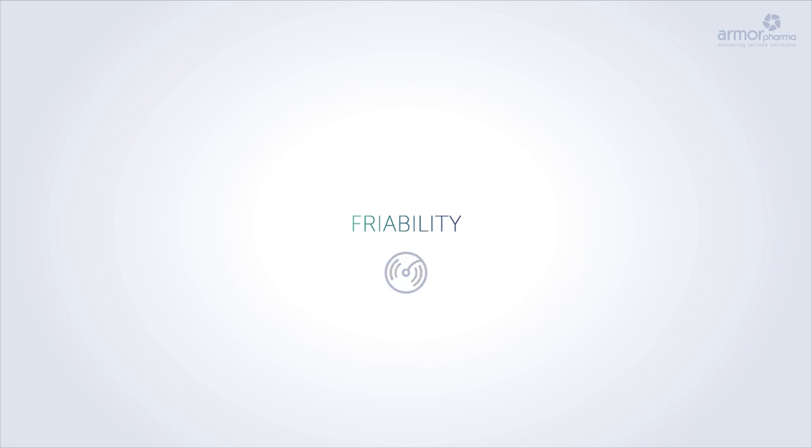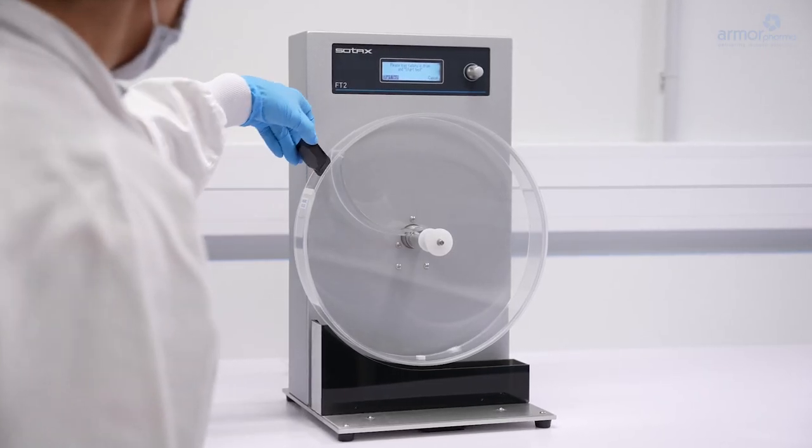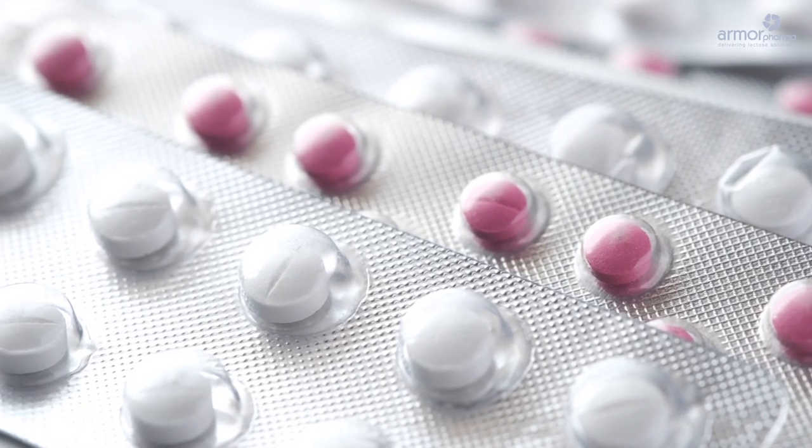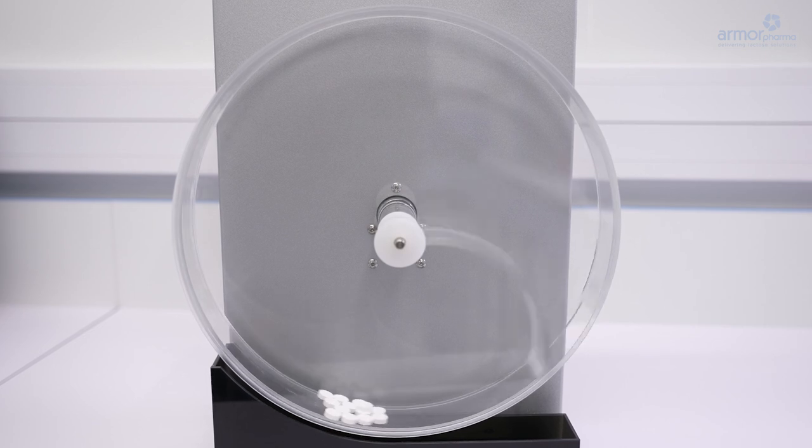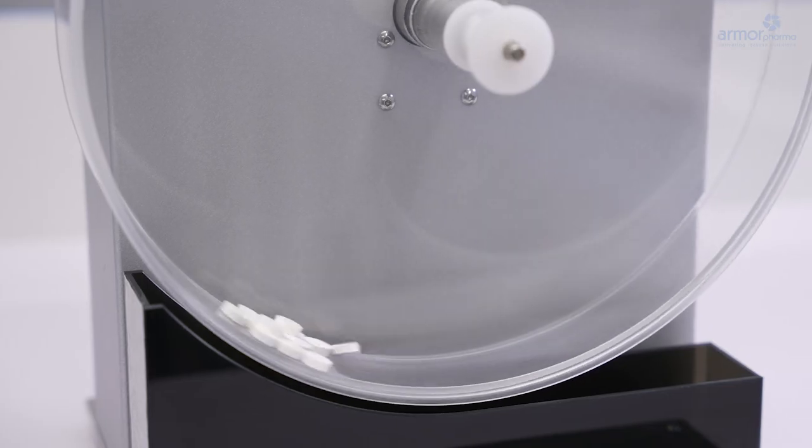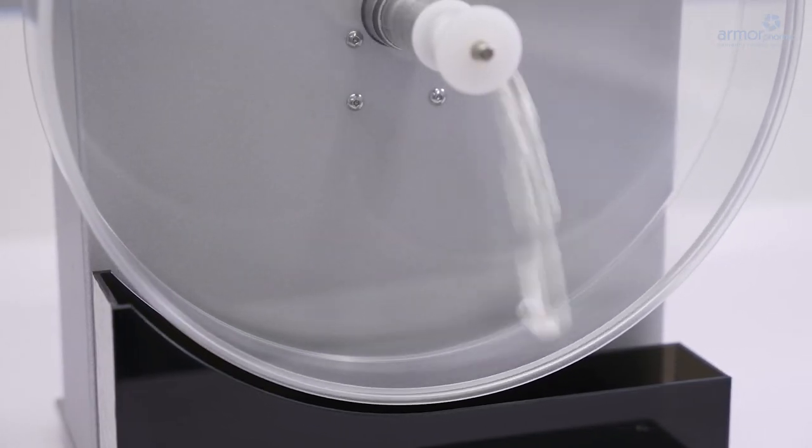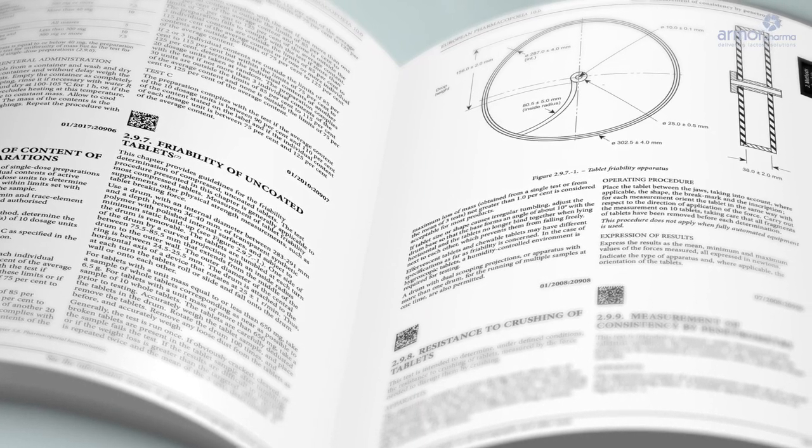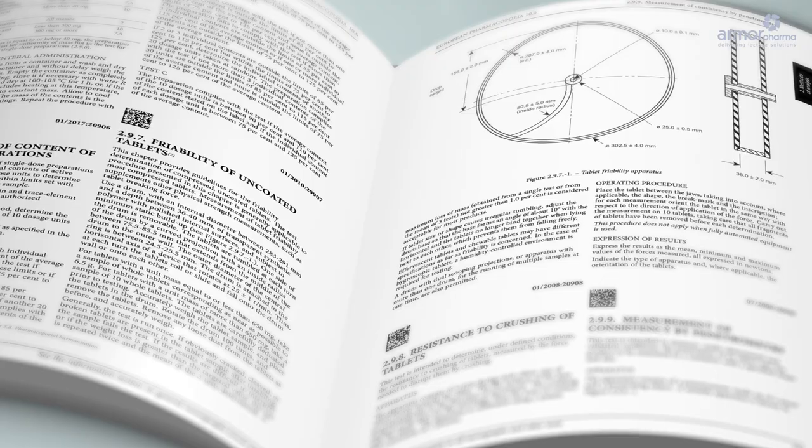Friability: This method is important to estimate the resistance of tablets during conditioning, coating and transport. The test consists of repeatedly dropping a sample of tablets over a fixed time using a rotating drum. The procedure and equipment used are fully in line with pharmacopoeia specifications.